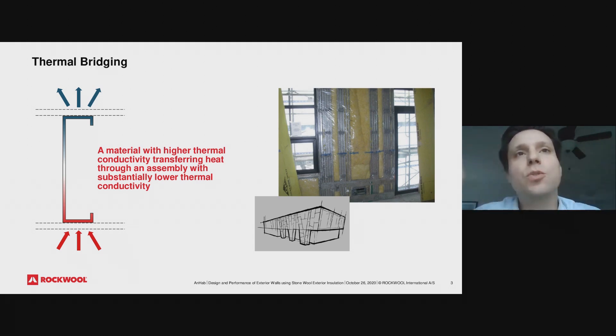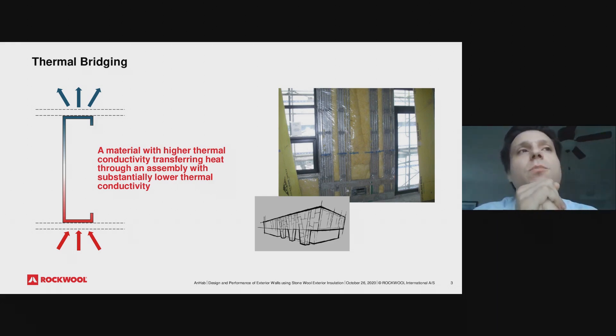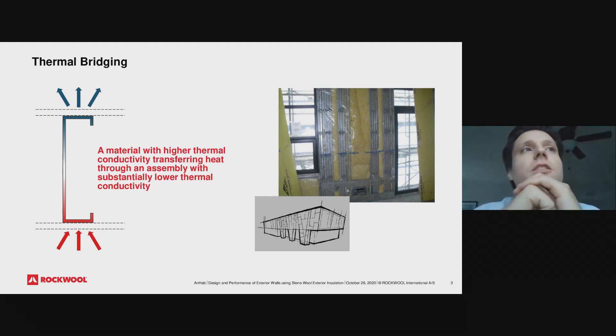In order to get proper performance, you have to address thermal bridging — not necessarily between the wall and a floor, but really the thermal bridging within the clear area of your assembly, such as through wood studs. Thermal bridging is basically when you have a material with a high thermal conductivity that is transferring heat through another material which has a much lower thermal conductivity. For instance, steel studs through batt insulation, or to a lesser extent but still very important, a wood stud penetrating through batt insulation.